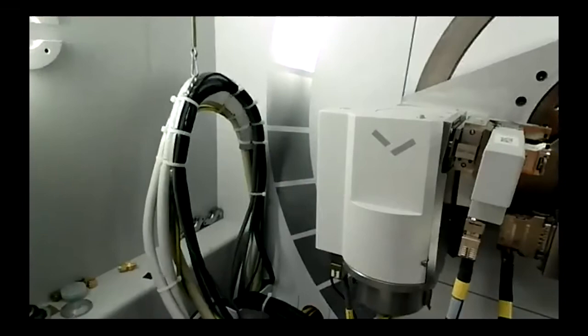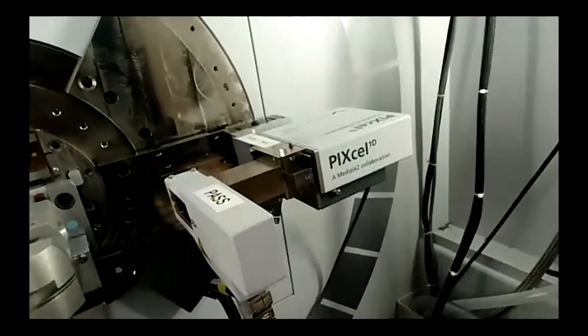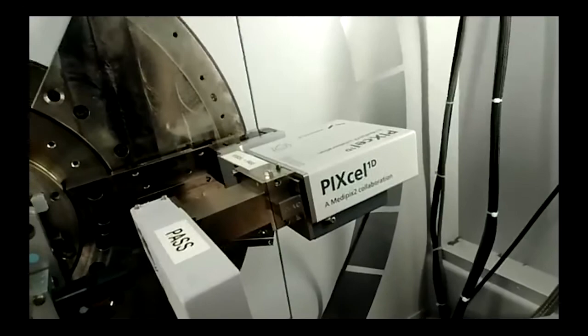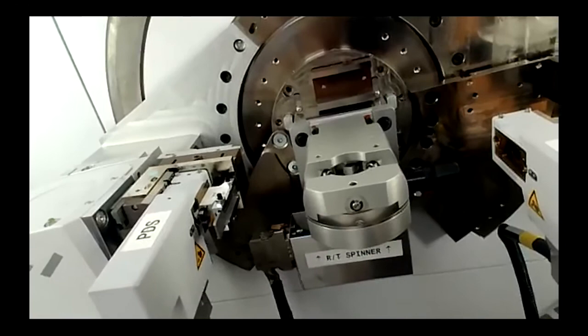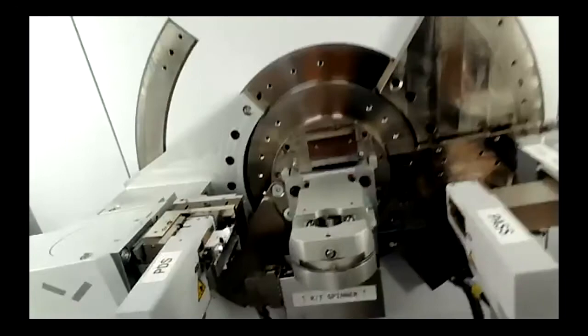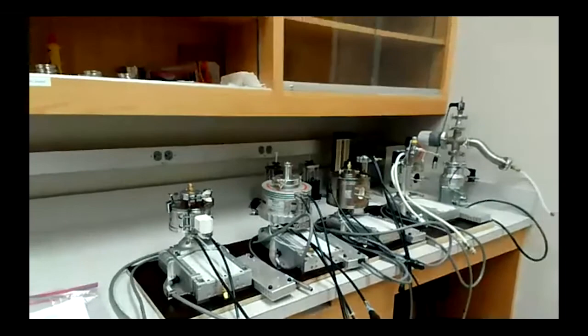On the left-hand side of this instrument, we have a copper X-ray tube — this is our X-ray source. On the other end of the instrument, we have an X-ray linear detector, which allows us to do very quick data collection. During XRD measurements, your sample will be sitting at the center of this instrument. What you are looking at right now is the room temperature sample stage. Besides this sample stage, we also have four non-ambient sample stages.